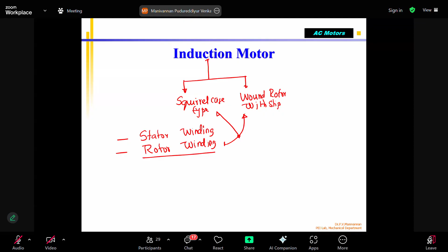That's why the motor itself is classified as squirrel cage type motor or wound rotor type motor. Please note that this is based on the classification of the rotor winding, how the rotor is wound, the connections, all this in the rotor. But as far as the stator is concerned, it is the same. There is a three-phase stator winding. The three-phase stator winding will be supplied with three-phase AC voltage. The rotor has no supply voltage, note down. In the rotor, only induced voltage is created.